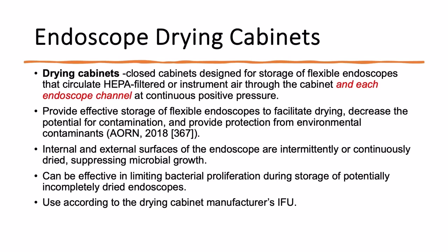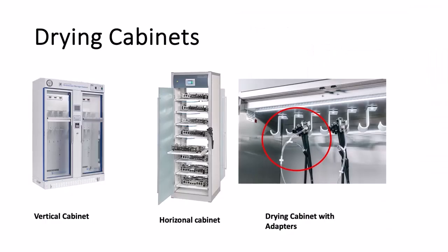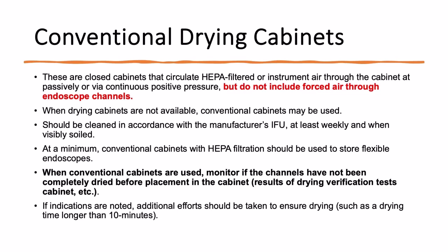So this is a storage cabinet. This is a horizontal storage cabinet, and this is the drying cabinet that has the adapters that adapt to the channels so that you have the HEPA-filtered air going through all of the channels, making sure they stay dry and bacterial-free. There are also closed conventional cabinets. These are closed cabinets that circulate HEPA-filtered or instrument air through the cabinet, but do not include forced air through the channels. When drying cabinets are not available, you can use a conventional cabinet.